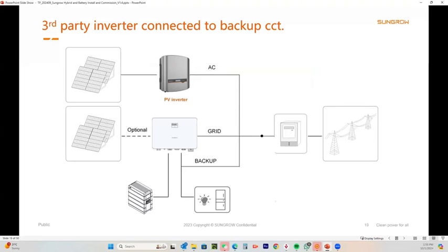Alternatively, one thing you can do is if you do have it AC coupled and you want the system to keep going, you can, under certain circumstances, connect that third-party inverter to the backup circuits. Okay, as long as this inverter is not bigger than the Sungrow. For example, if you've got an SH5 RS, this can be anything up to 5 kilowatts, but not larger, okay? And it must be able to respond to frequency shift. Now, you know the AS4777 says if the frequency goes above 52 Hertz, then the inverter must shut down. That's how it operates. So in the off-grid mode, if the system is producing more than the batteries and the loads are going to consume, it does have to ramp down.